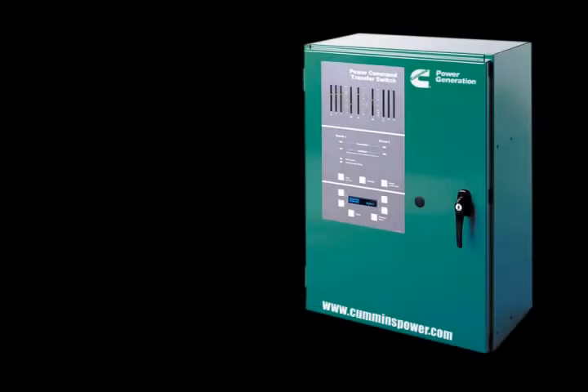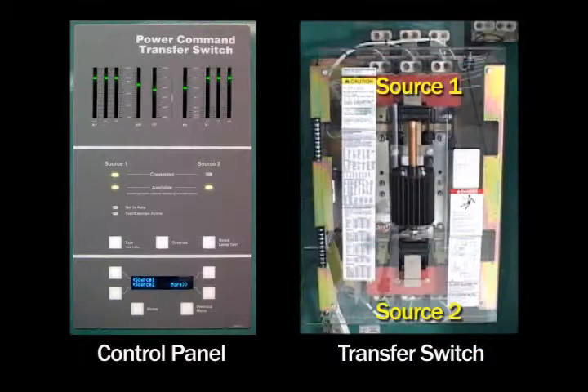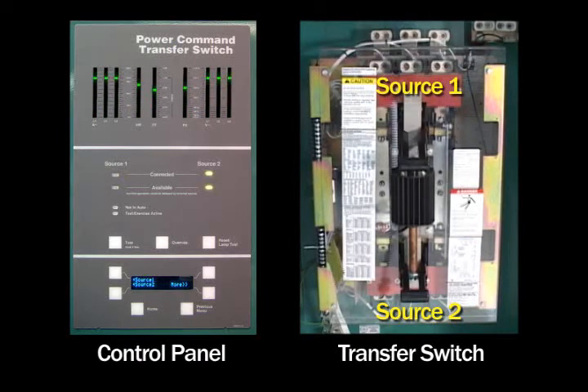The automatic transfer switch has a digital control which monitors the condition of both power sources. If the control senses instability or a loss of power, it will transfer the load to the alternate power source. When conditions return to normal, it will transfer back to the preferred source automatically.